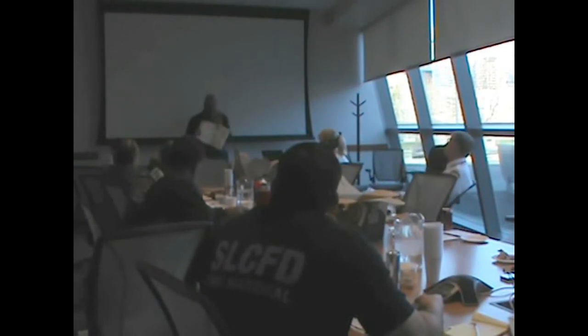All fire escapes must be complete to grade. So any fire escape that I have a ladder that's 8 feet from the ground, guess what it's missing? 8 feet. It's missing the 8 feet, which the code said back in the 40s, back in the 20s. It says you can complete the other 8 feet by doing what? A ladder or a cantilever. But people read that law and did what? They stopped at that sentence and said, hey, the law says 8 feet, so that's why you have 8 feet.